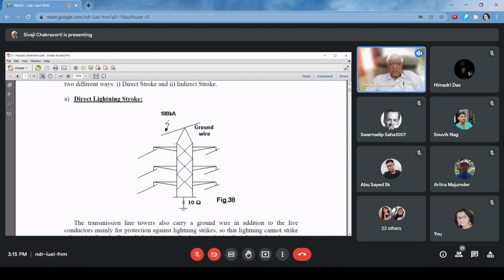Now, if it is 300 ohms, even with 10 kiloampere, which is a very common lightning, the voltage becomes 300 ohm into 10 kiloampere, which means 3000 kV, which is very, very high voltage. If that voltage appears, nothing can prevent a flashover. So we have to somehow ensure that the lightning doesn't strike the conductor. If the lightning strikes the tower, what happens?